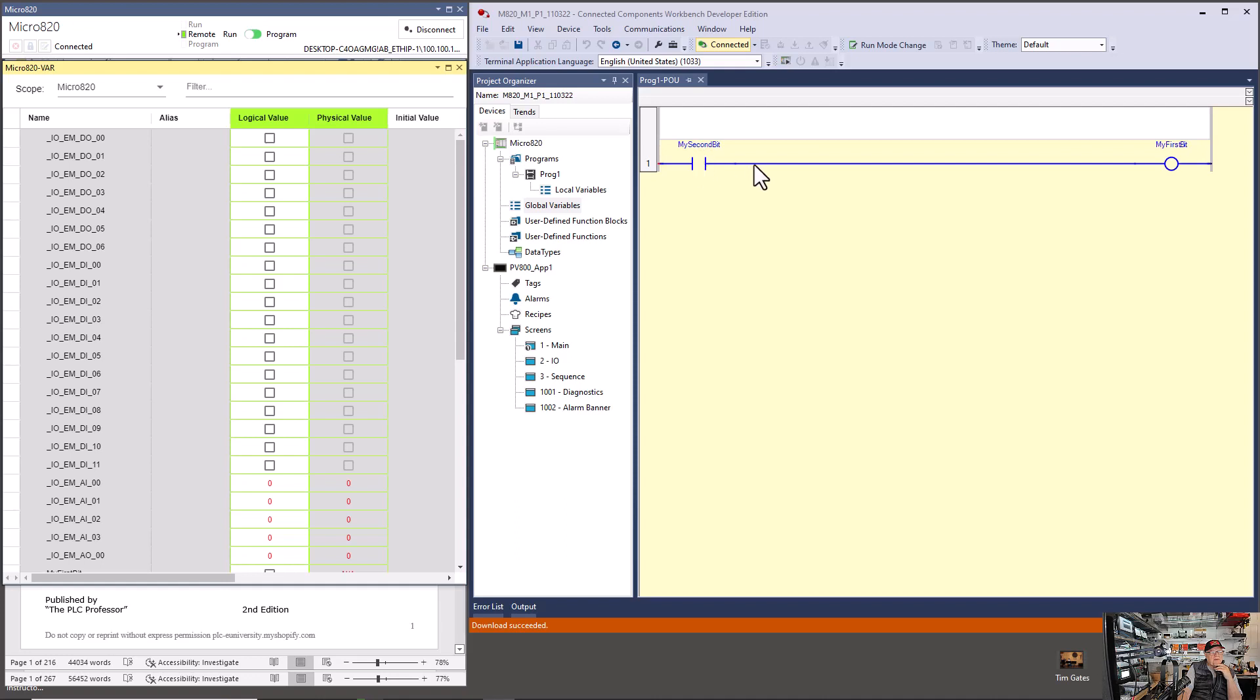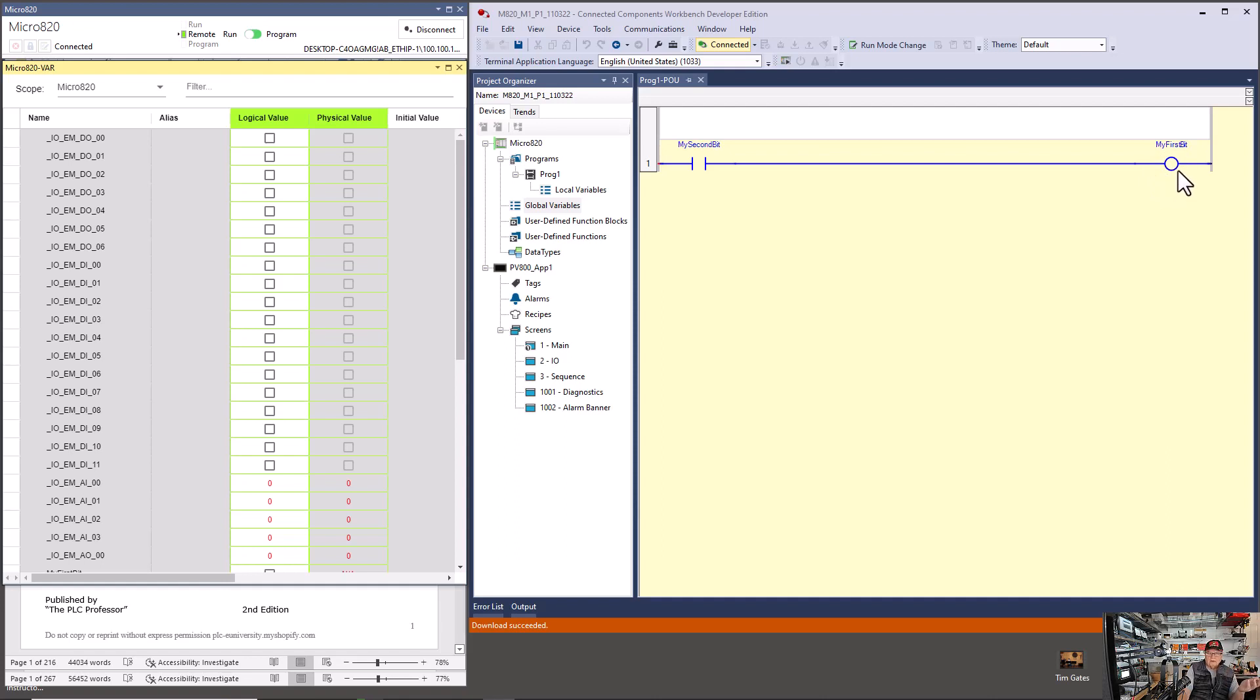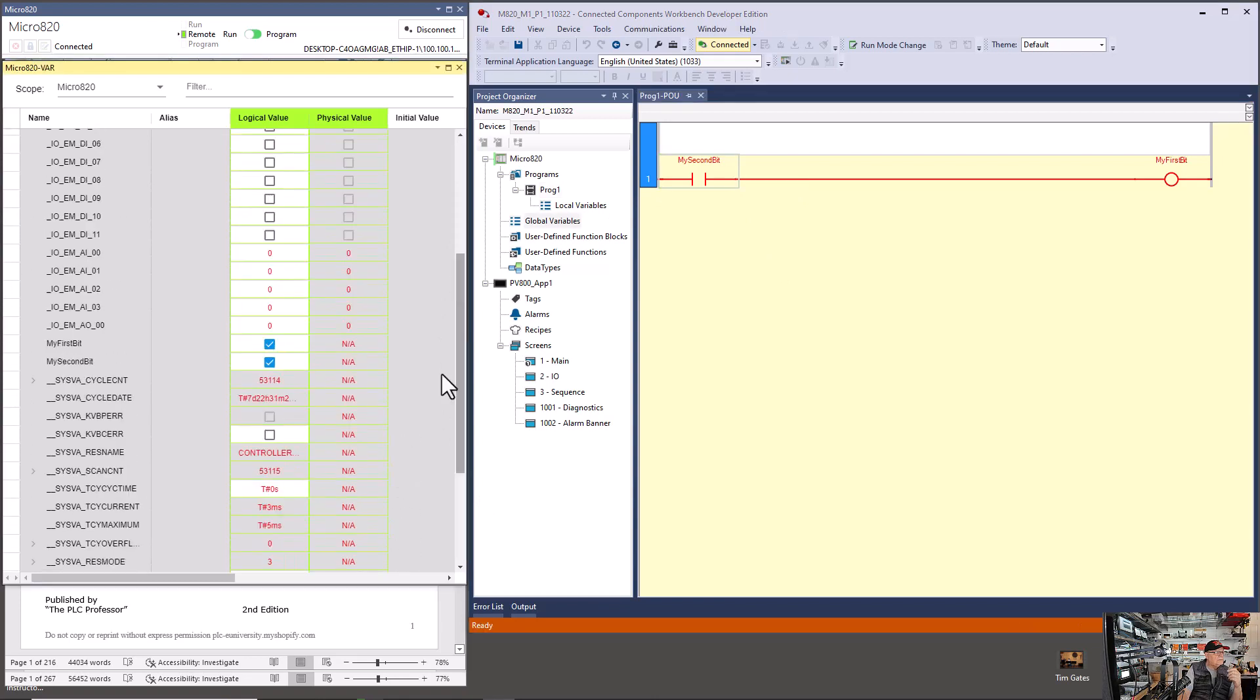This rung says if this bit is on in memory, then this is true. Then turn on this bit in memory. We're reading my second bit and this instruction right here is true if this bit that it addresses in memory is on. It's off right now. My second bit, the text is blue. When you see blue text, that means off. When you see blue instruction, especially on this half, that means false. This instruction right here will follow the state of this bit. This instruction right here, this OTE looks like a relay coil. It is never true or false. The rung is true or false. The instructions are true or false.